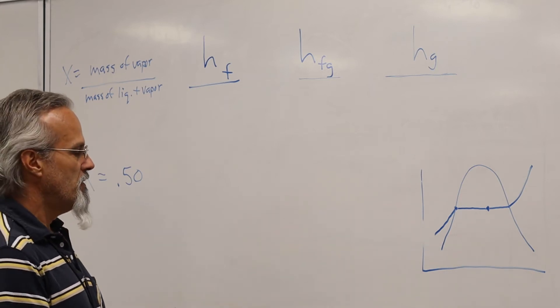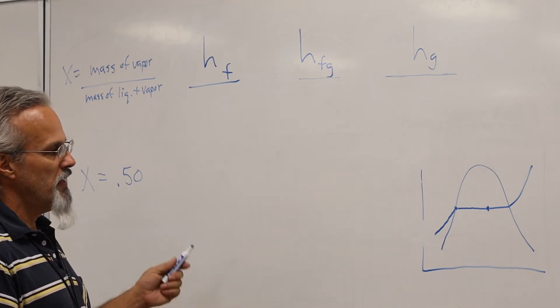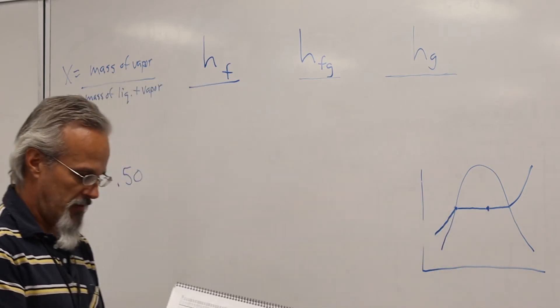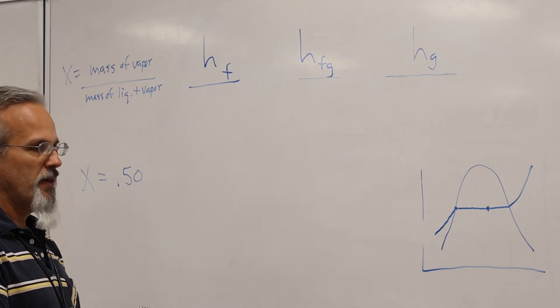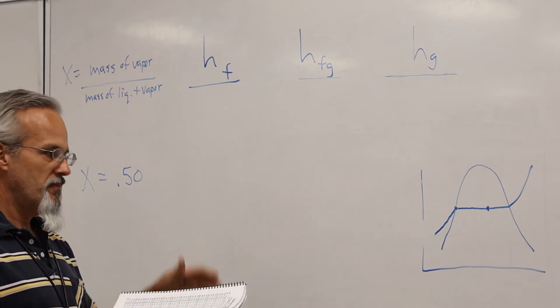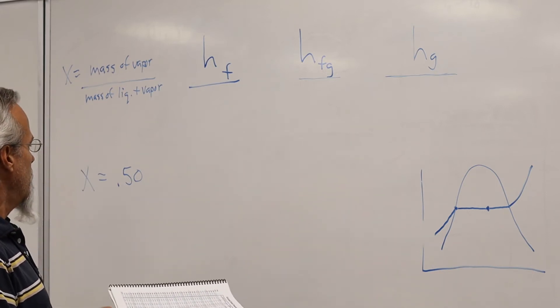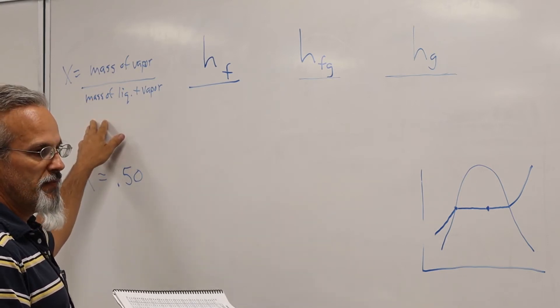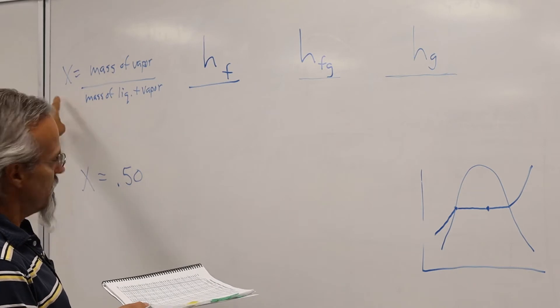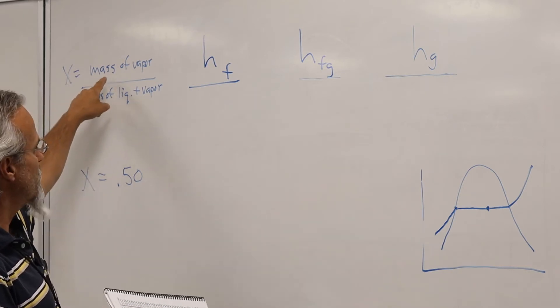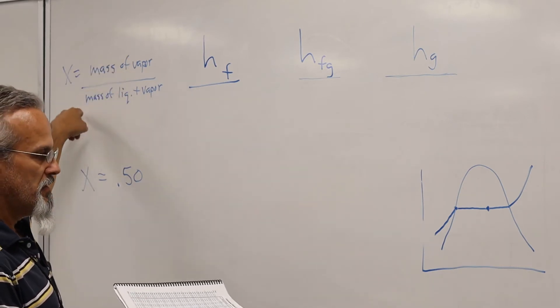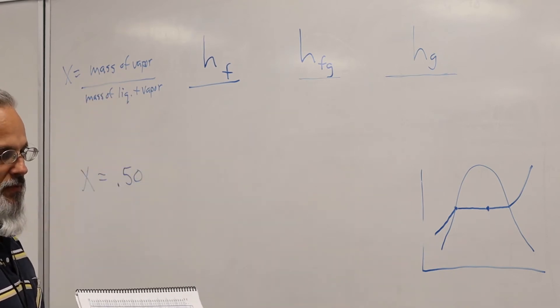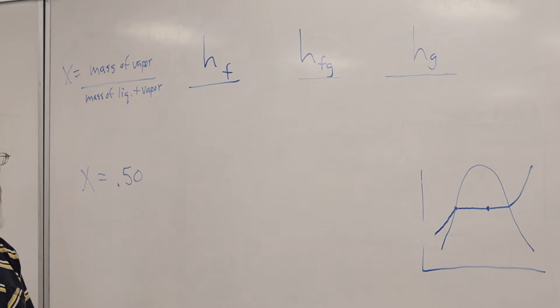So if we are at some in-between state and we want to calculate the total enthalpy of the system for that particular state point, we would use the steam quality factor, given the symbol X — it's going to be the mass of the vapor divided by the mass of the liquid and vapor phases total. So it's going to be some fraction less than 1.0.